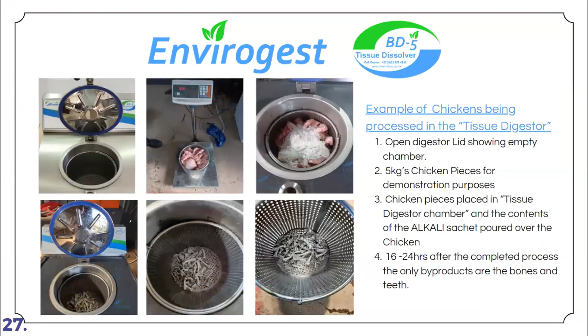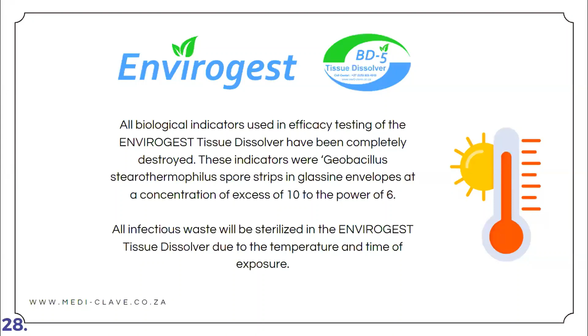All biological indicators used in efficacy testing of the Envirogest tissue dissolver have been destroyed. These tests were the Geobacillus stearothermophilus spore strip in a glassine envelope at a concentration in excess of 10 to the power of 6. All infectious waste will be sterilized in the Envirogest due to the temperature and the time exposure. So previously, I mentioned the vital parts of sterilization is time, temperature, and pressure. And again, in the Envirogest, it's time, temperature, and pressure.